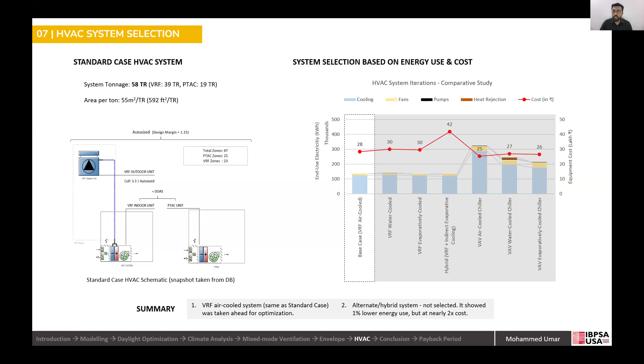Optimizing the base case forward, the optimization strategies used were replacing all the PTAC units by VRF, so all the 21 zones were also now catered by VRF, optimizing the zoning and right-sizing the equipment, changing the fan type, and of course, introducing humidity control, because it's a warm, humid climate zone. So that was very important. That reduced the overall EPI by 11%, the highest reduction of any of the strategies by far. The standard case had 58 tonnage of auto-sized equipment. The optimized case had 49 tonnage. So the final EPI of the HVAC optimized system was 66.2 kilowatt hour per meter square per year.